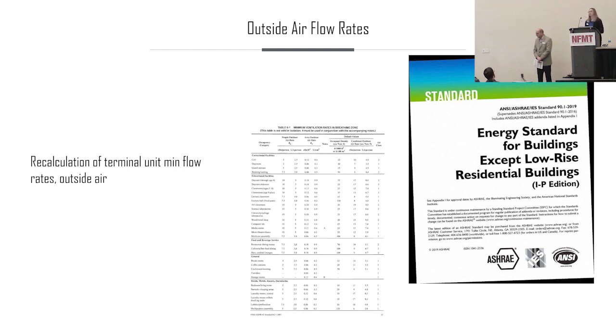Another way to consider how much outside air you're truly bringing in besides space type: during the design process, your occupancy for your outside airflow rate calculations, not all the times, but a lot of times, are based on default values that ASHRAE gives you. If you know your occupancies have changed or they're not as high as those default values, especially after COVID when a lot of people aren't in the space anymore, you could bring in less outside air to have to ventilate for those people.